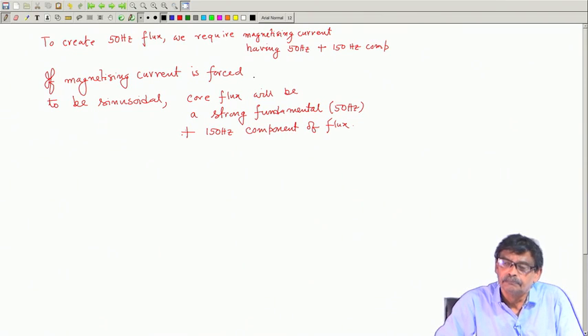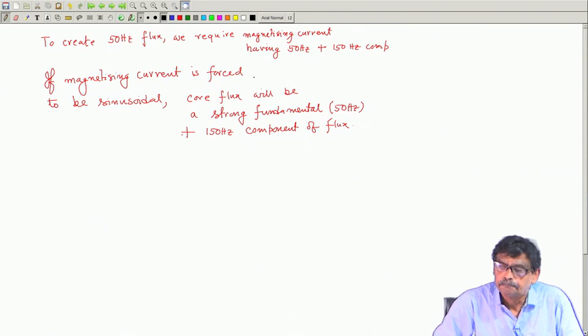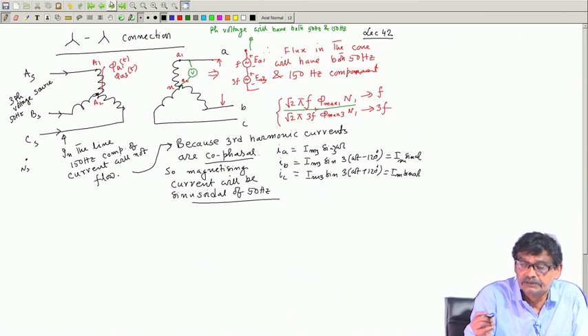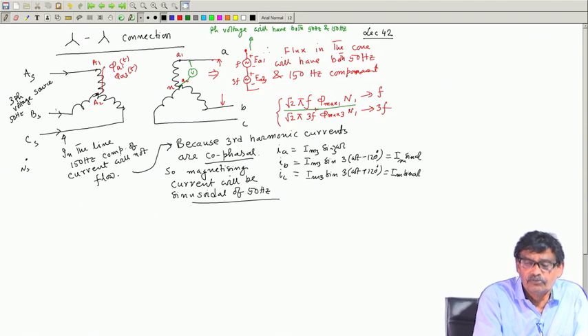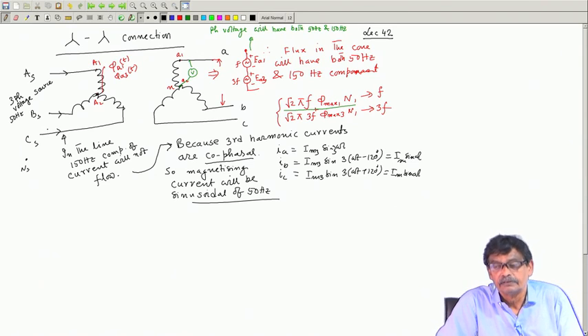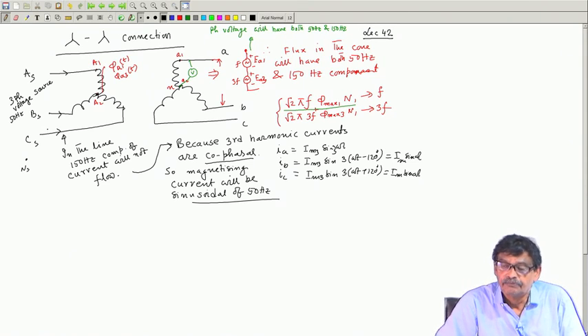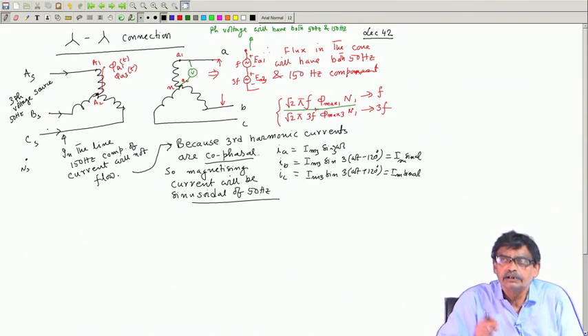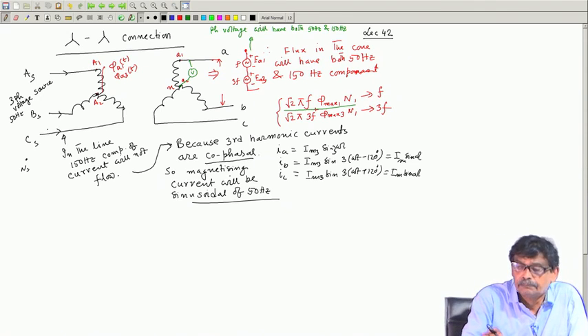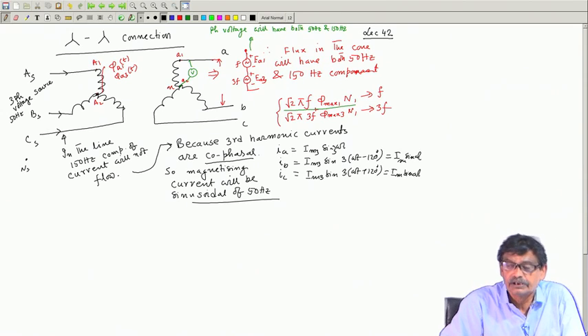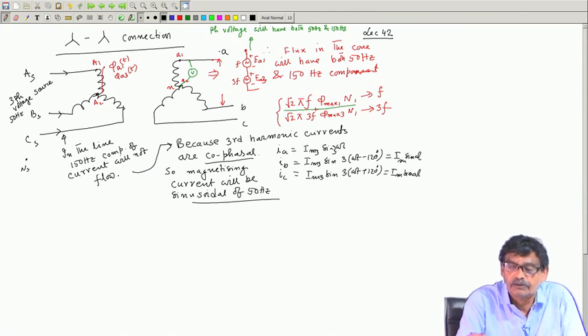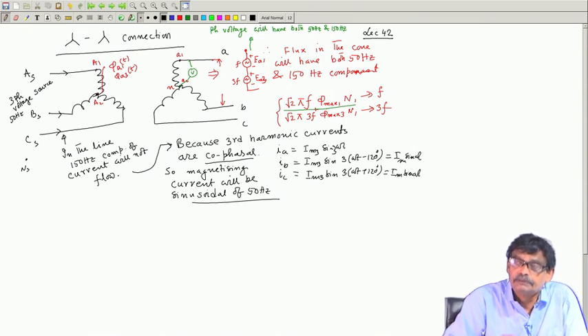In the case of star-star connections without any neutral connected, there is no scope for any third harmonic current component to exist in the lines. Therefore, the flux must have both 50 Hz and 150 Hz components. Higher order harmonics are also present but their amplitudes are smaller. The phase voltages will be distorted, although the line-to-line voltages will have only 50 Hz components. But phase voltage will have that 150 Hz component.